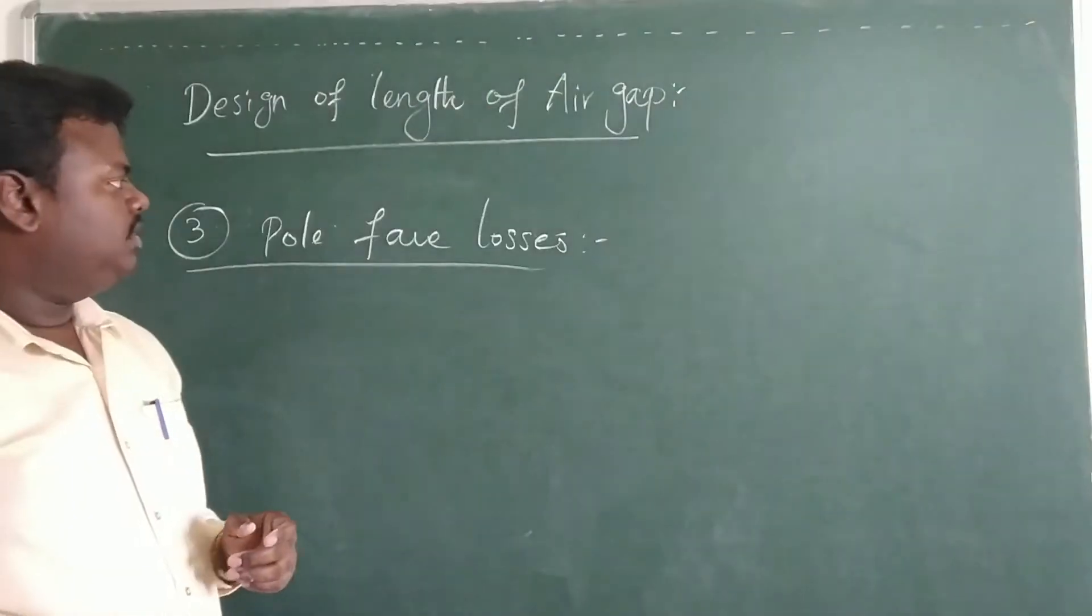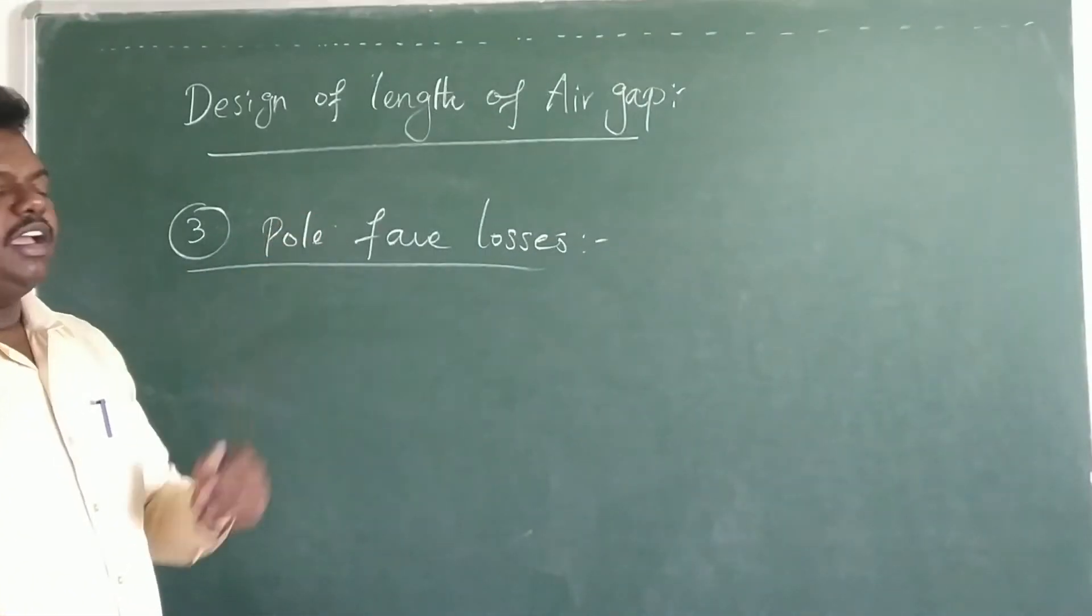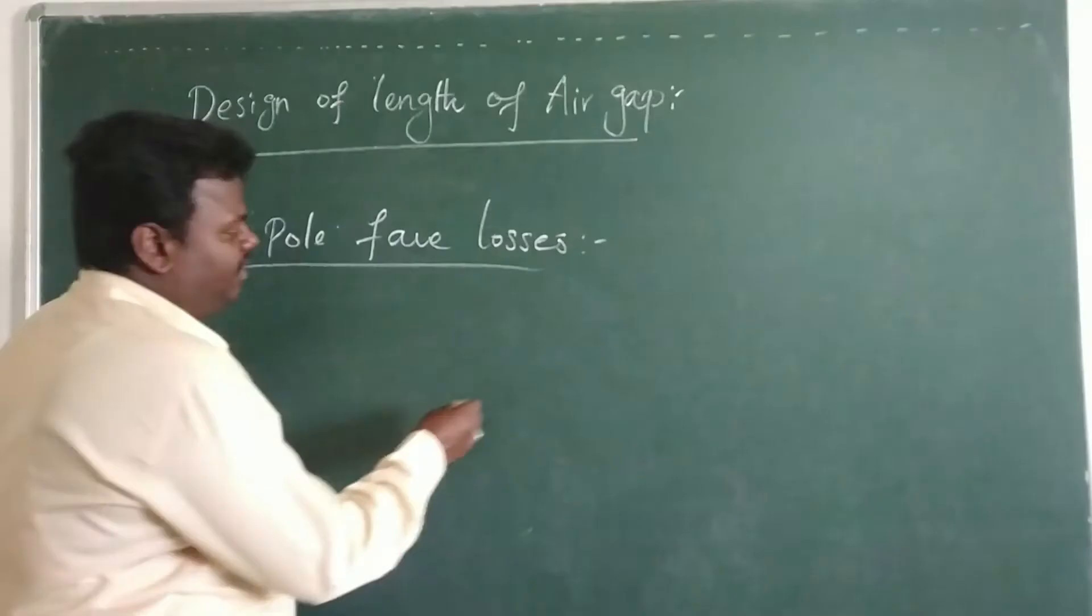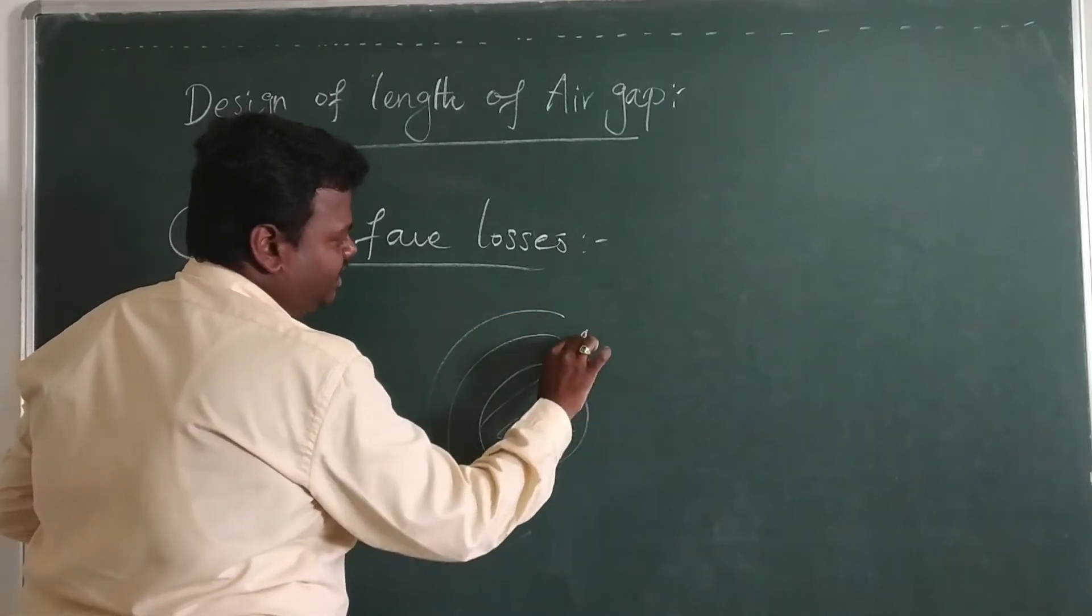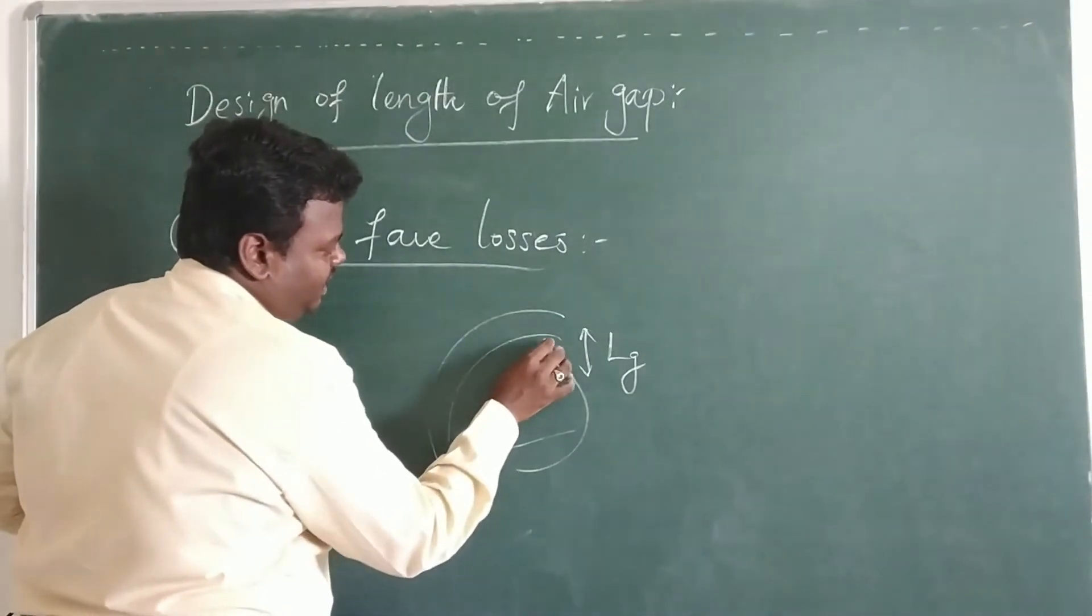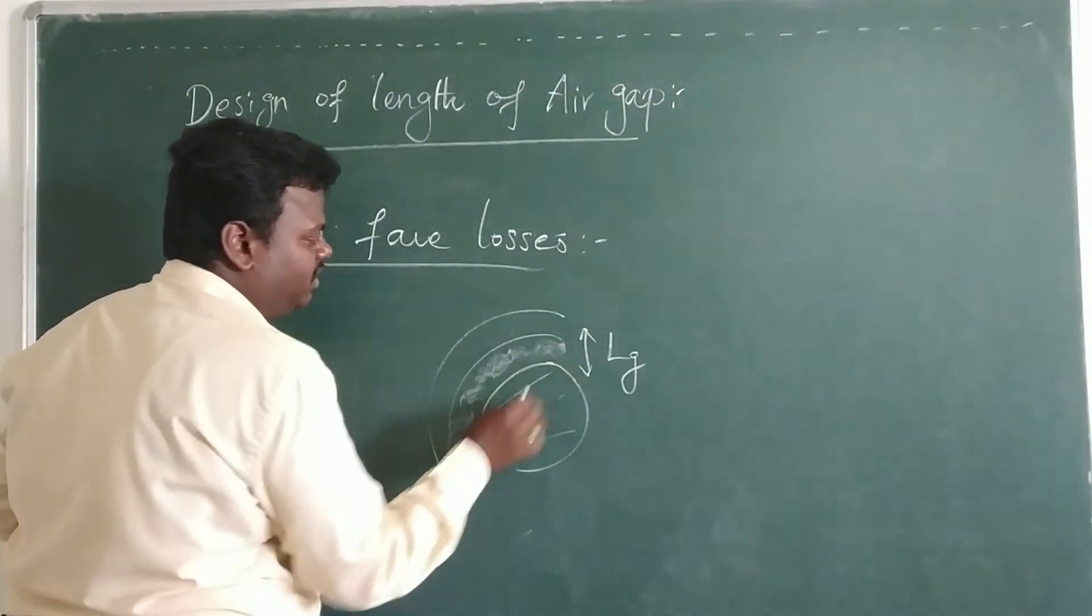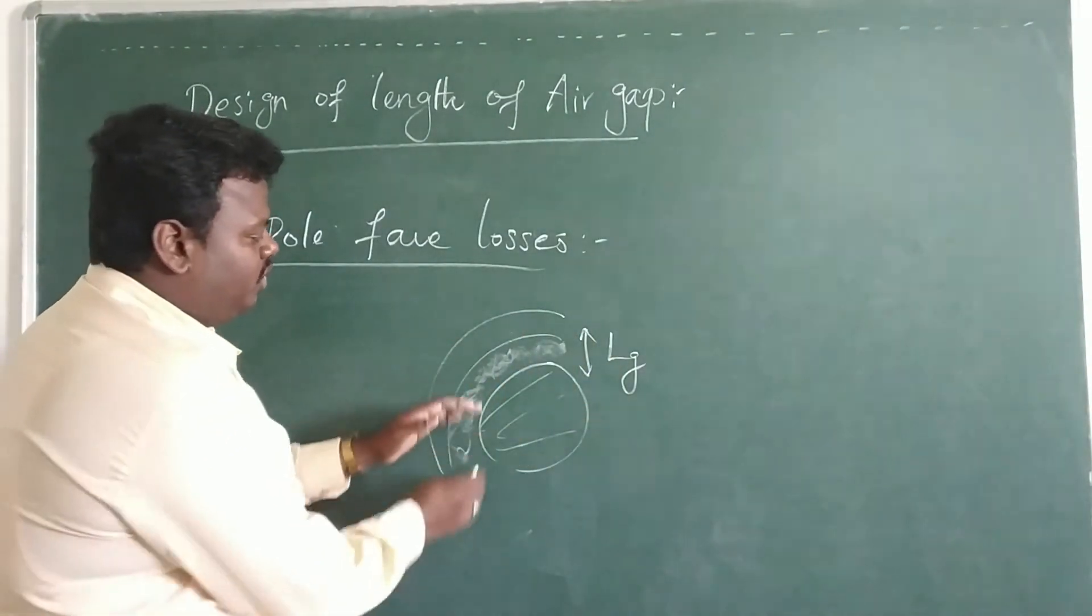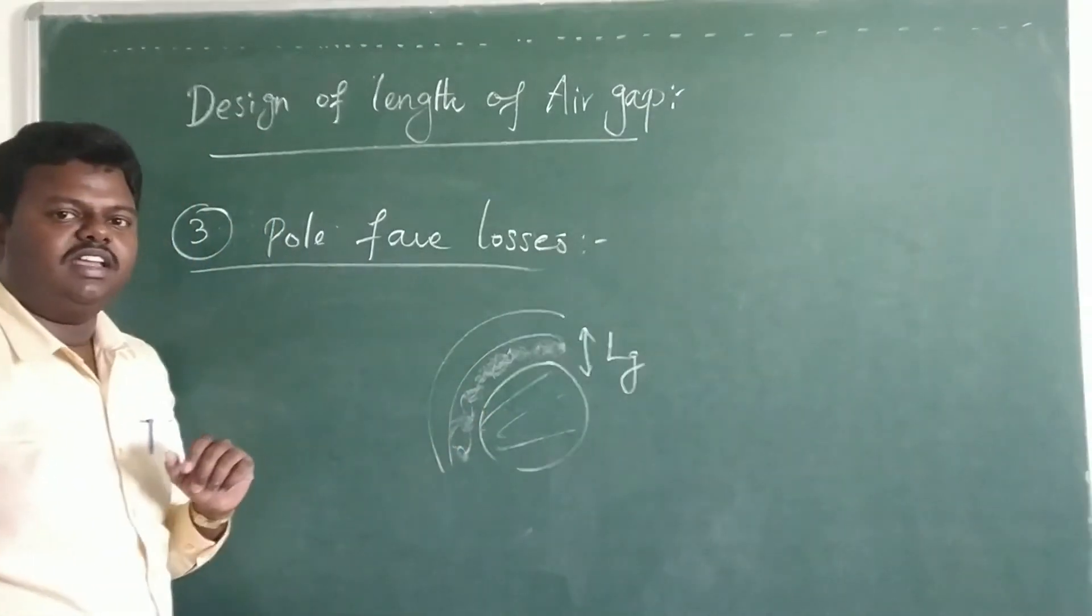The third parameter which disturbs the air gap length design is pole face losses. Whenever we keep the air gap length larger, what actually happens, the flux density present in this particular air gap will reduce, due to the large amount of this air gap length. So due to this, the pole face loss in the particular core will get reduced.